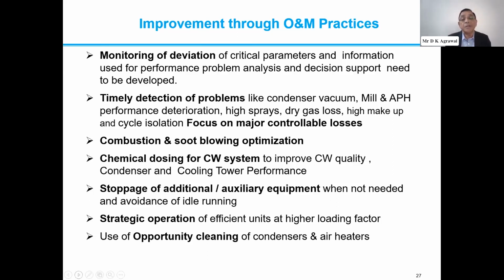Sometimes I have seen, particularly in the case of the condenser, that it may be worthwhile to take a short shutdown and do some cleaning of the condenser and come back, maybe just the top half of the condenser, because major deposits are on that. You will be very much benefited. You can definitely make an assessment of what the DP across the condensers is, and then take those types of decisions. But it is worthwhile many times. Next slide, please.